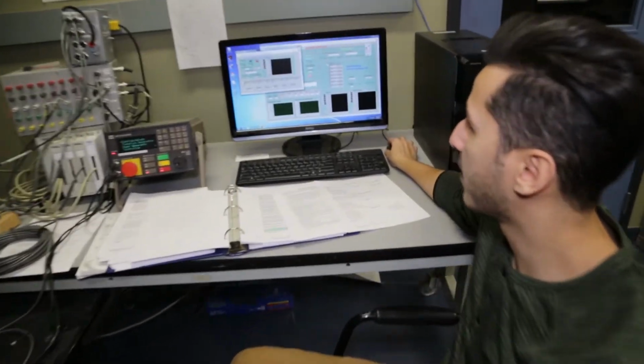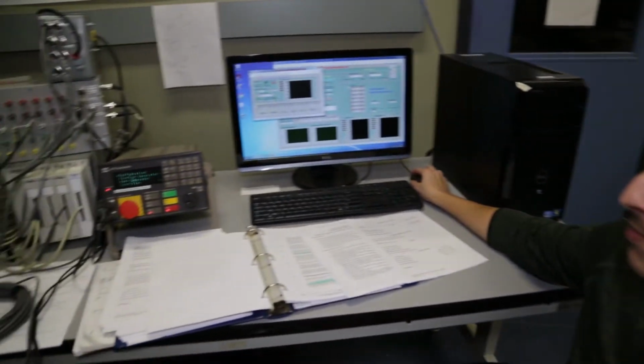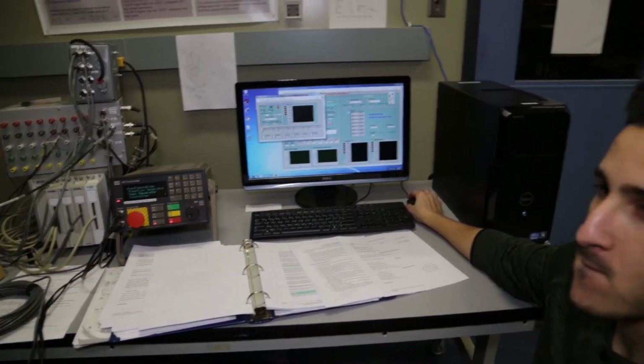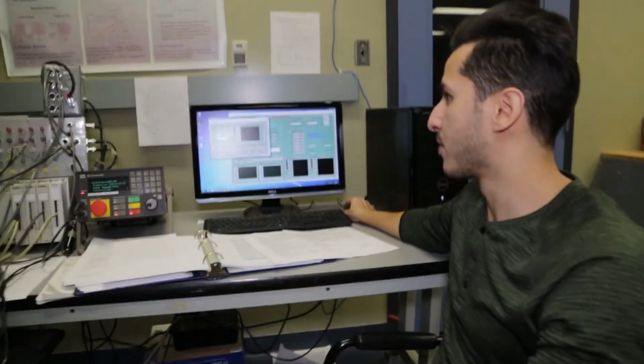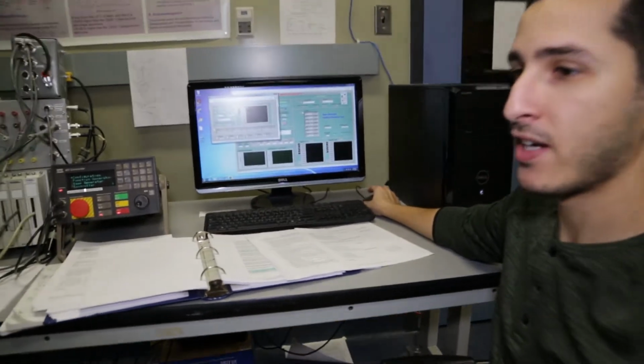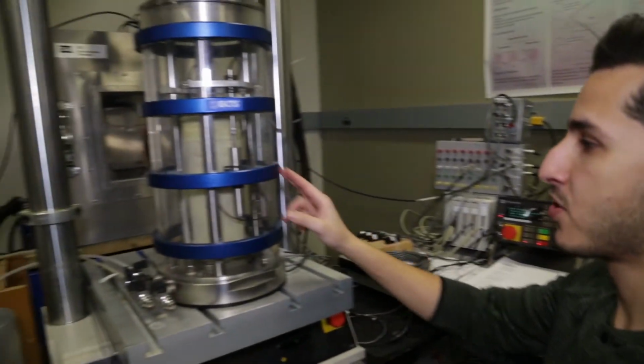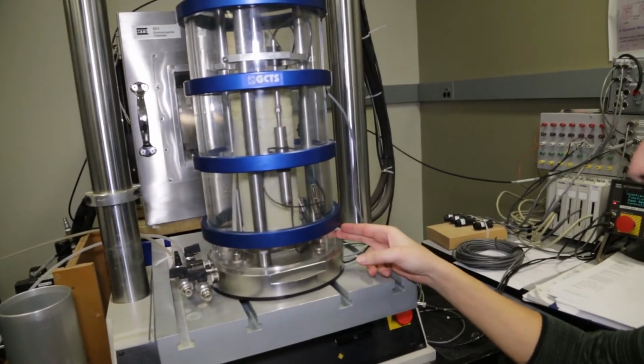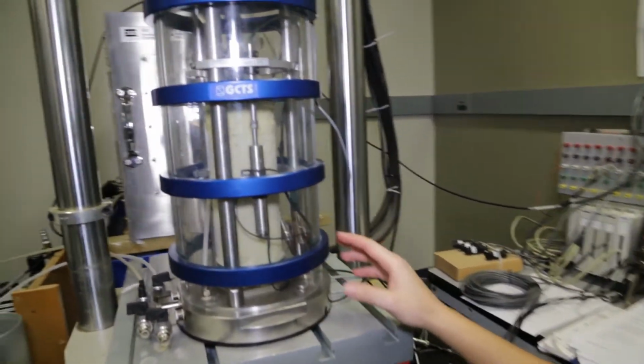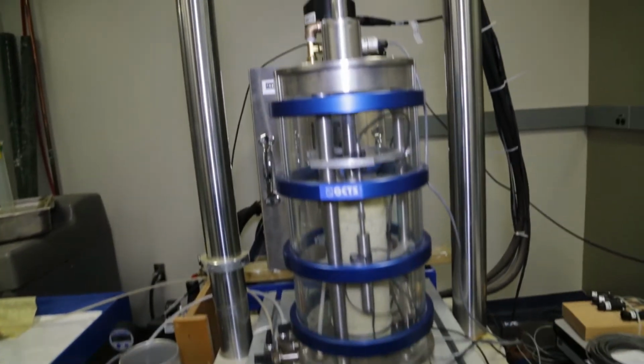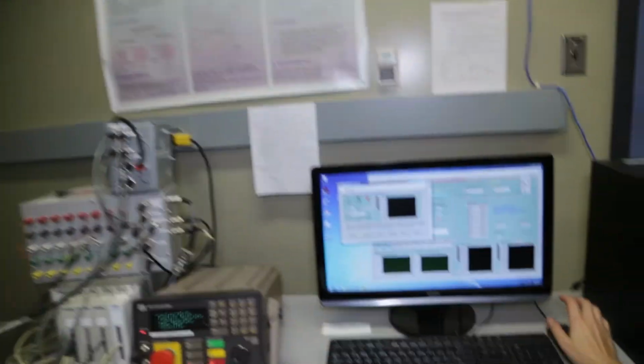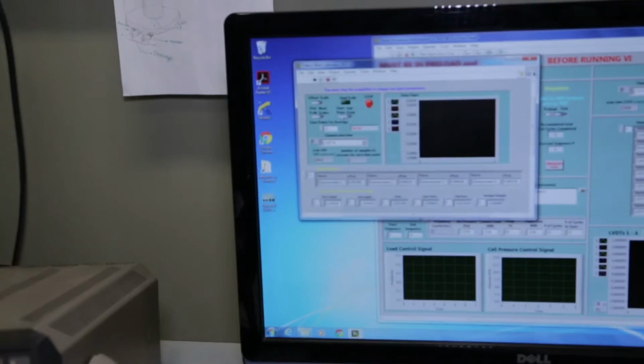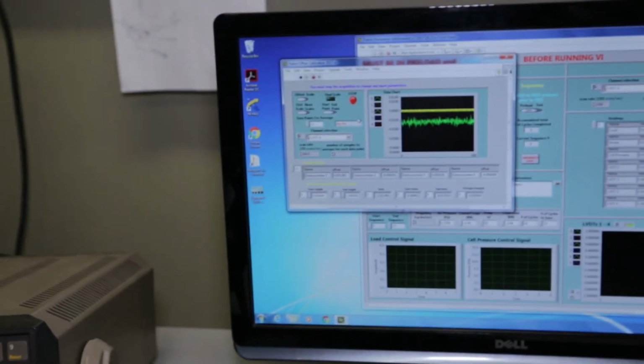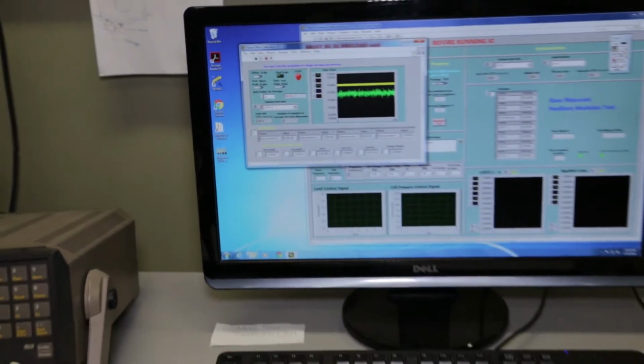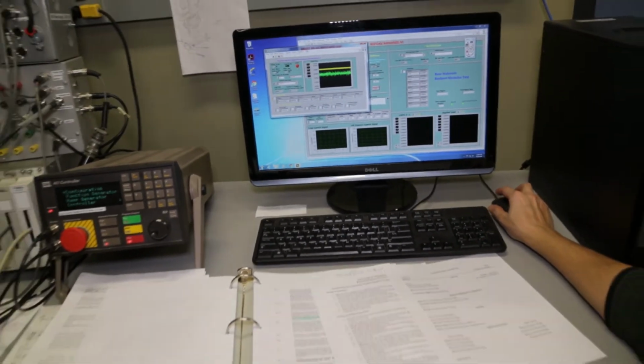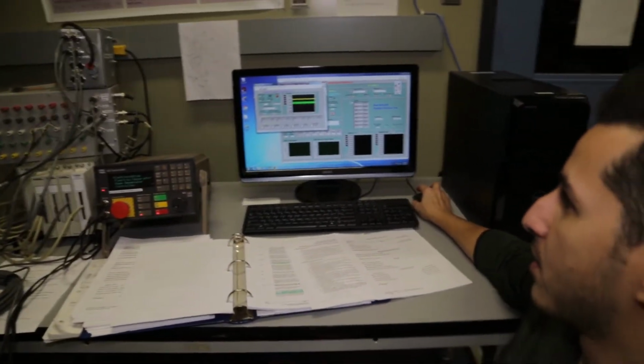Now I open the offset calibration program to make sure all the sensors are starting from 0. So before I run it, I make sure that all the connections are connected and nothing is loose. Then I click run on the offset calibrations. It takes a few seconds, maybe 14 seconds, until it sets off and asks you to stop.